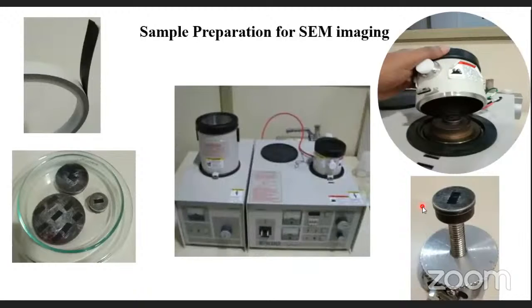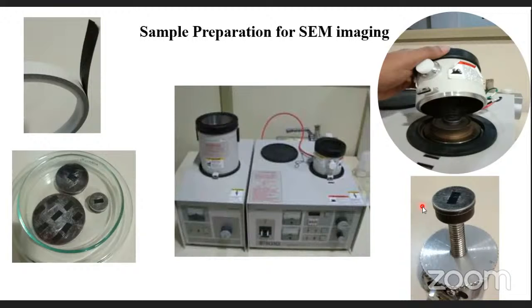An important basic point that postgraduate students, faculty, and research scholars working with materials need to understand is how to prepare a sample for SEM imaging. The main point is that samples analyzed with SEM must be completely dried — otherwise it will disturb the vacuum and ruin your imaging. Another critical point is that the sample should be conductive.